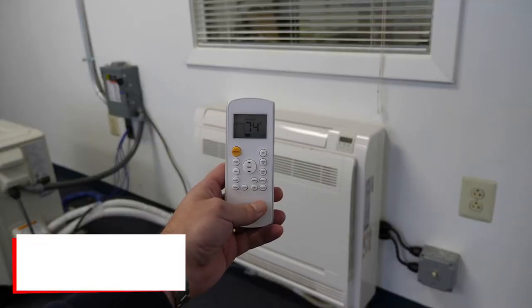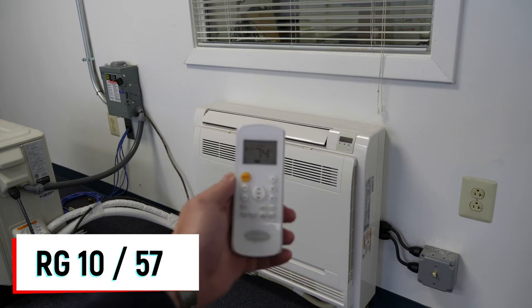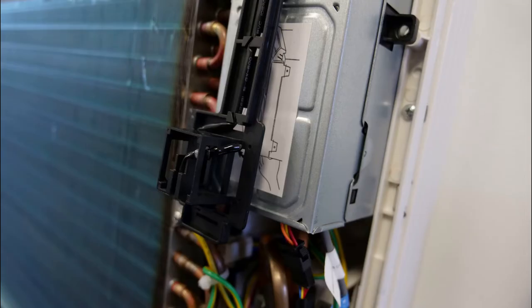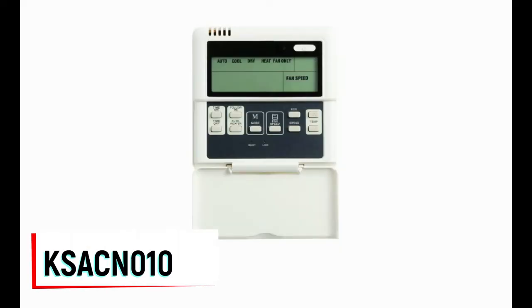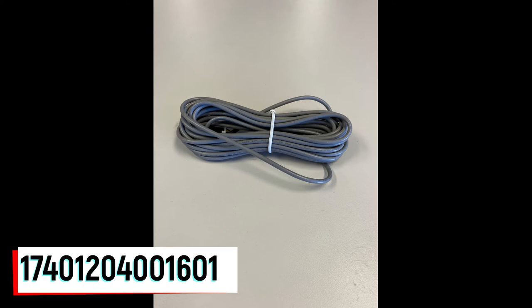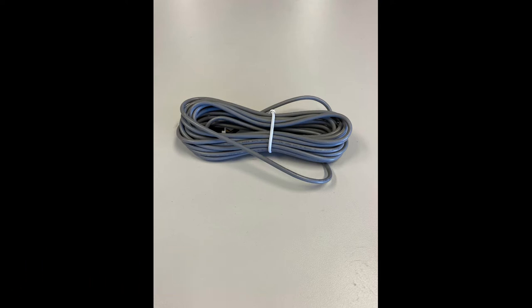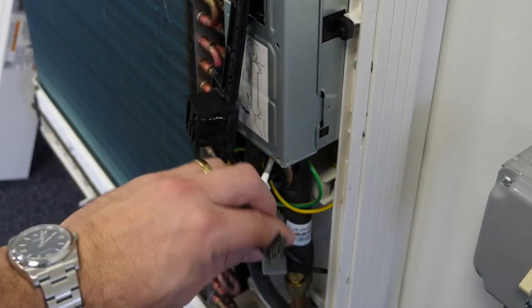Out of the box, the unit comes ready for operation via either the RG57 or RG10 wireless remote, and senses temperature from the previously shown return air temperature sensor. All 12 through 58,000 BTU sizes are compatible with the KSACN-010 wired controller. The control comes with its own proprietary cable, which may be extended up to 160 feet using multiples of the part number below. This cable connects to a harness located under the front panel of the indoor unit.